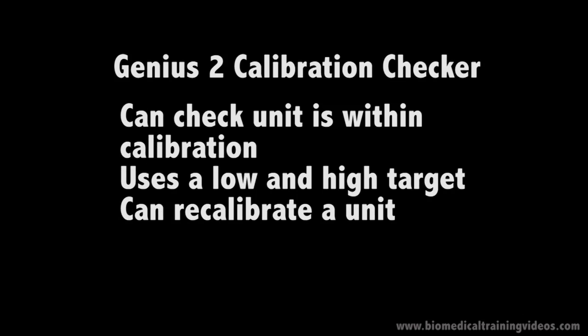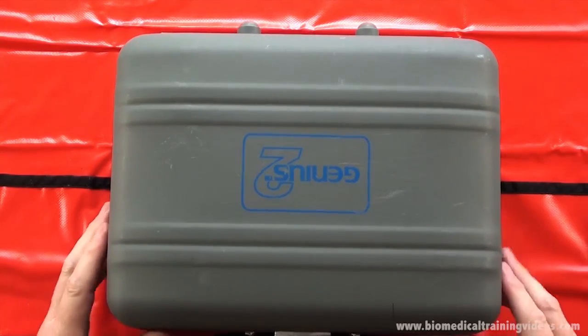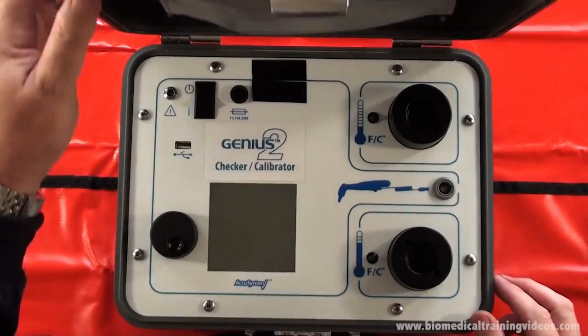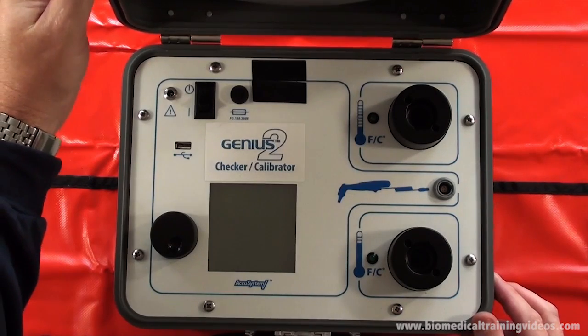So the Genius 2 calibration checker has two parts. One is to check the unit, and the other is to perform a calibration if it's not performing to specification. It does this by using a low and a high target. It is dedicated to the Genius 2 thermometer. So here we are, just having a look at the unit itself. Very solidly put together, a carrying case.